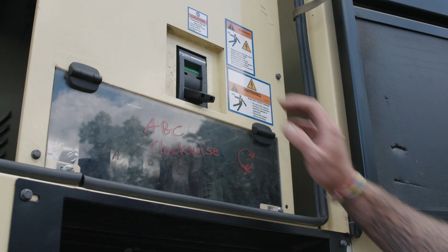One is facilities tend to oversize generators for future expansion. They buy now hoping to expand later. So that generator could sit there for a few years running at around 30% load. Well, a diesel is most efficient at around 80% load, and that's when it's burning all the fuel out of the cylinders. So to run 3-4 years at 30% load, eventually that raw fuel is going to start sticking to the inside of the exhaust and slowly closes it off.